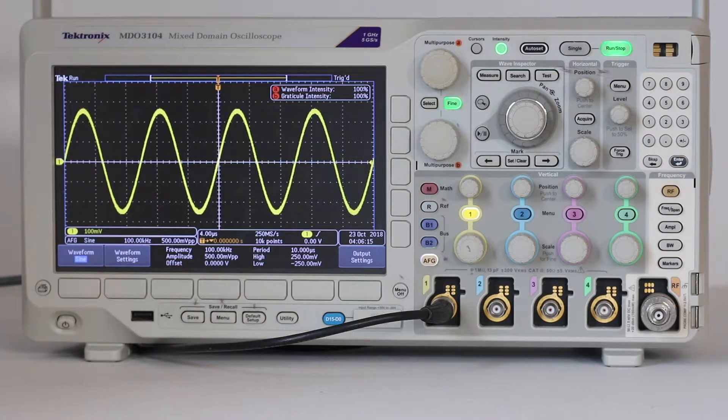The single scale knob in the horizontal section can be turned by the user to expand or compress the time interval within each of the ten industry standard horizontal divisions. In that way, the waveform depicted spreads out until it appears to be an almost flat line.